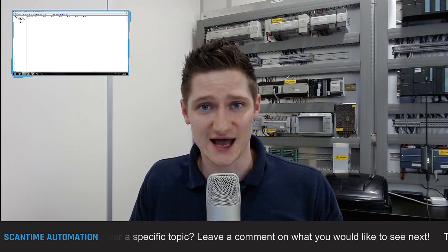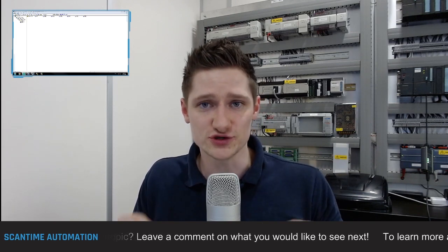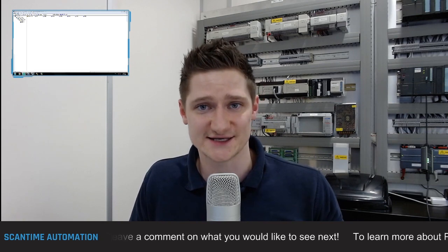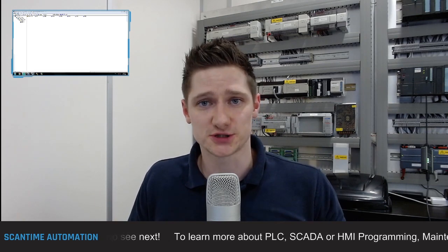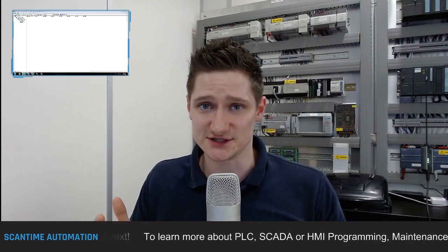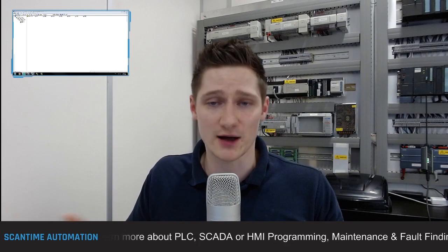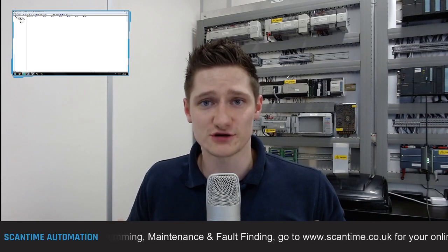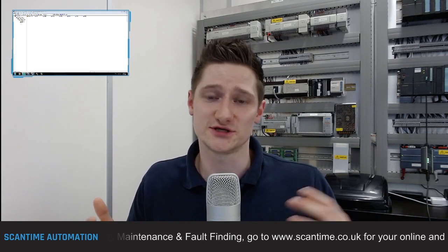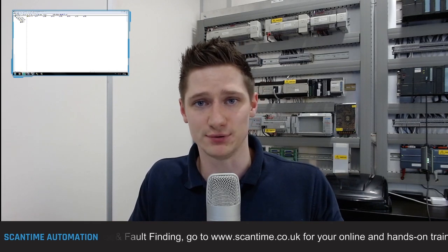Now Siemens does have another set of counters inside of STEP7, and those are inside of what it calls the SFBs, the System Function Blocks. These are actual function blocks created by Siemens and stored on the CPU of the PLC, meaning that when we use them, we don't have to download them to the PLC, they're already on that PLC. Just like any other function block inside STEP7 or TIA portal, we must always assign an instance data block to that.